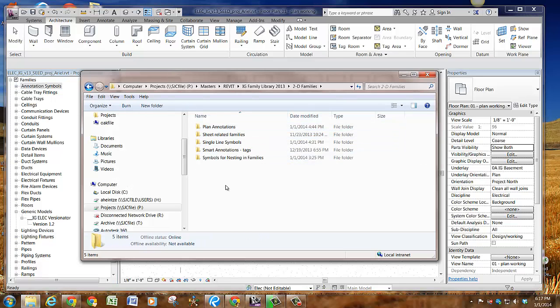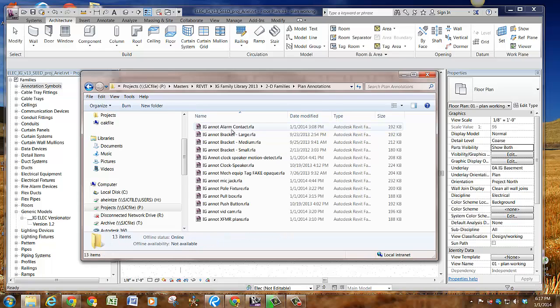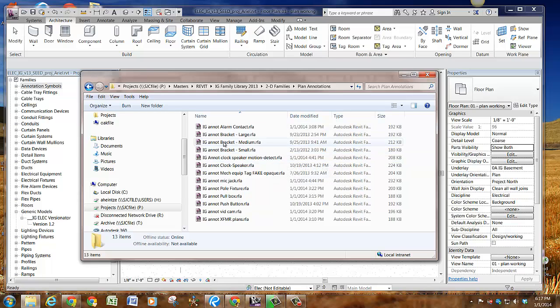The first thing I want to talk about is how we label 2D families. 2D families for the single line diagram will have SLD in front of them. Families used as a symbol without any 3D content will have IG and then ANOTE for annotation in the front. If it has annotation in the front, you know it's a type of annotation you can use by itself. Other families may be named with annotation at the end — generally those are nested in other families and we don't use them by themselves. Look for ANOTE at the beginning for using 2D symbology.